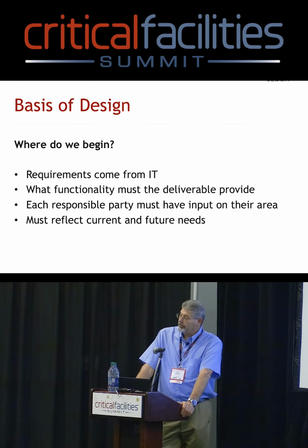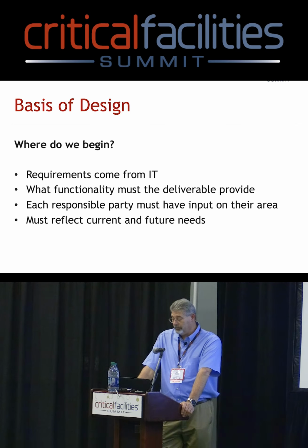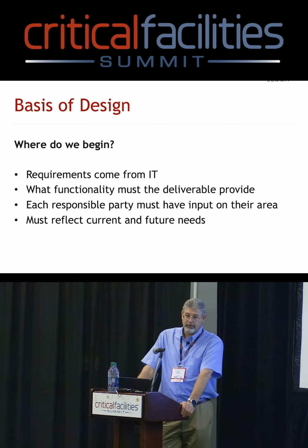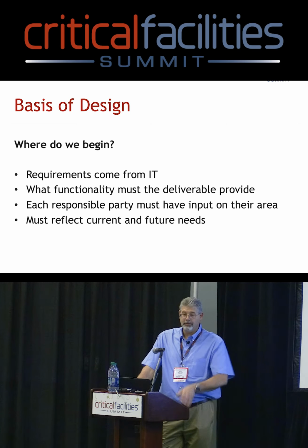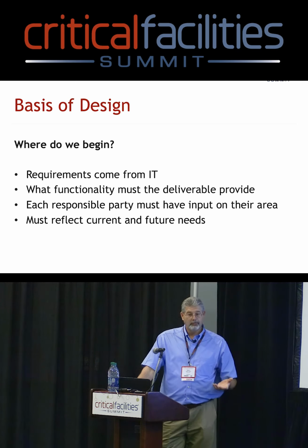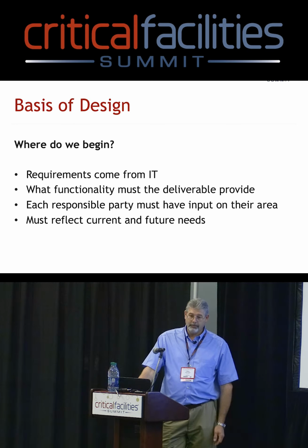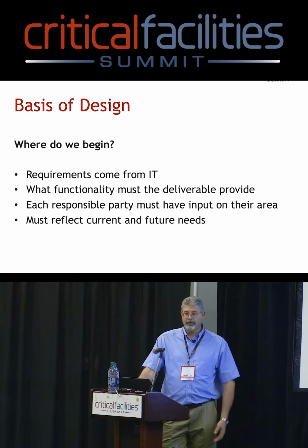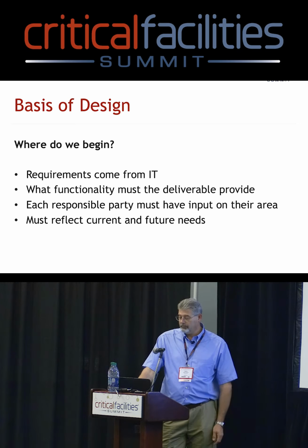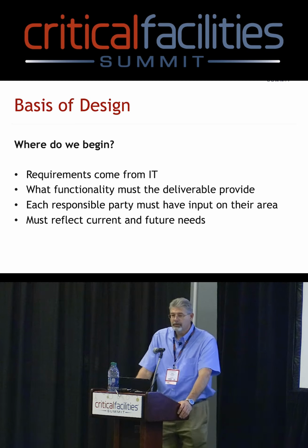You can look at your voltage that the equipment is going to run on. Can you get everything in there on 208? You can go higher voltage, lower amperage, you're a little more efficient. You can use better power supplies, but you've got to talk to the IT folks, because if they just order it, then they don't have the knowledge that we share. They don't really think too much about efficiency of a power supply. They don't think too much about the power factor at the incoming, the service entrance to the building.